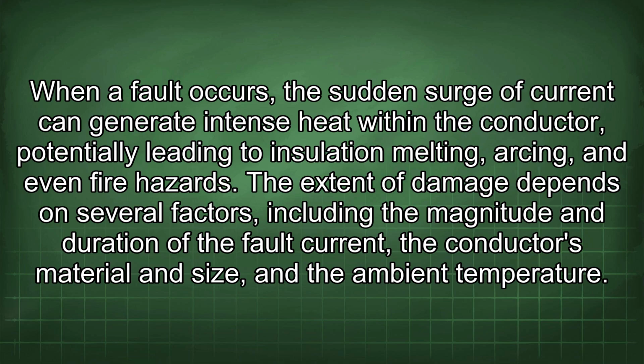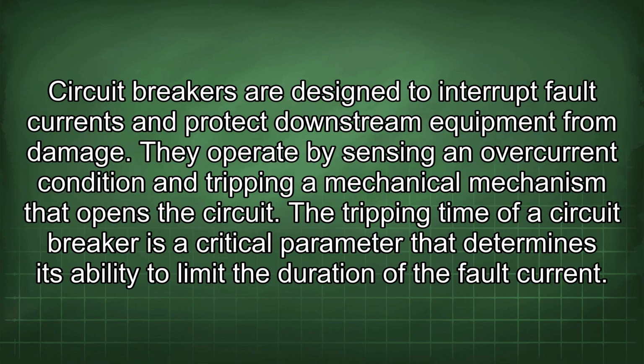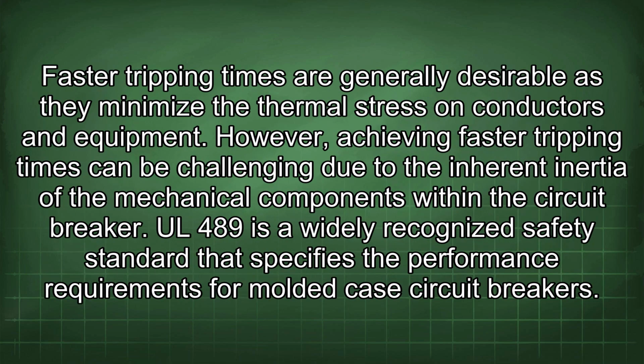The extent of damage depends on several factors, including the magnitude and duration of the fault current, the conductor's material and size, and the ambient temperature. Circuit breakers are designed to interrupt fault currents and protect downstream equipment from damage. They operate by sensing an overcurrent condition and tripping a mechanical mechanism that opens the circuit. The tripping time of a circuit breaker is a critical parameter that determines its ability to limit the duration of the fault current. Faster tripping times are generally desirable as they minimize the thermal stress on conductors and equipment.